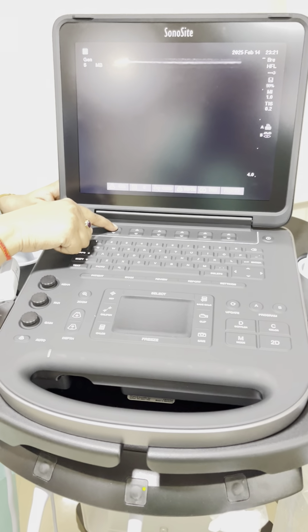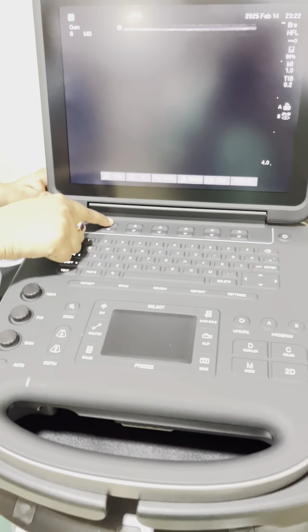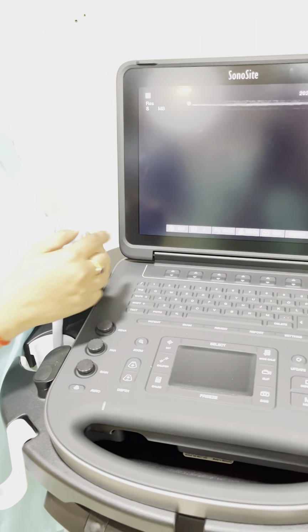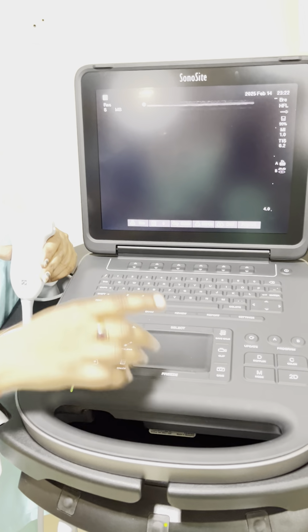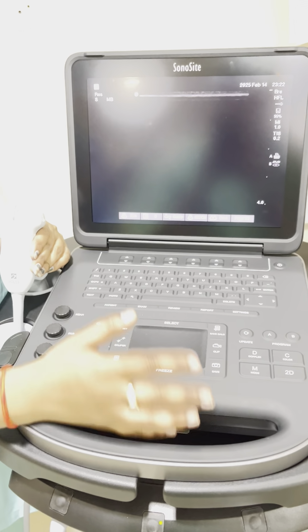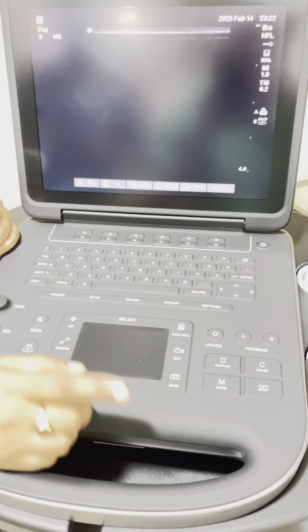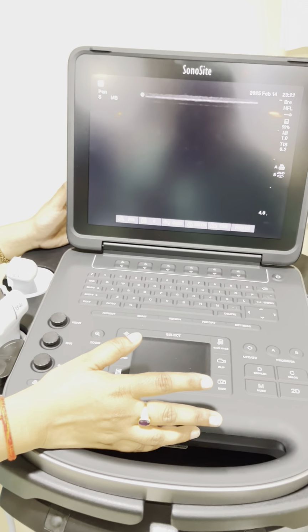This is 3 different options for your resolution settings. One is general. General works on the mid frequency band, and resolution works for superficial structures, means it works on high frequency band, and it will give you superficial structures more clear. And when you are working for deeper structures, you can put on the penetration mode. Your lower frequency will work at that time and you will get the better resolution for the deeper structures by putting on the penetration mode.